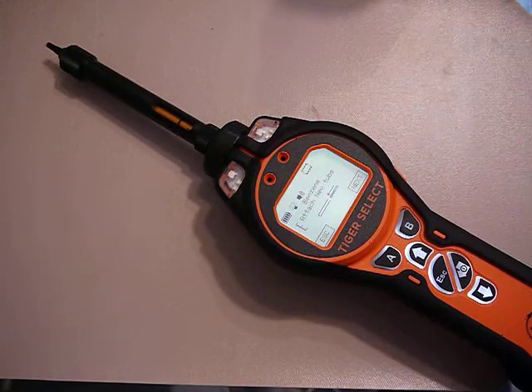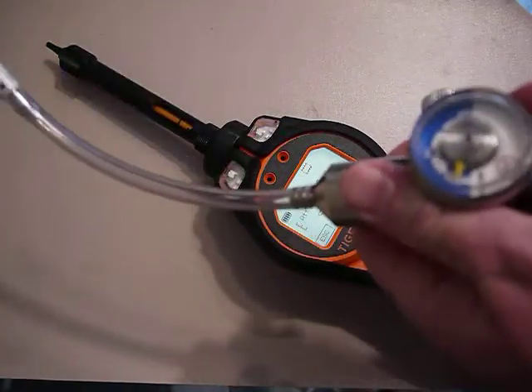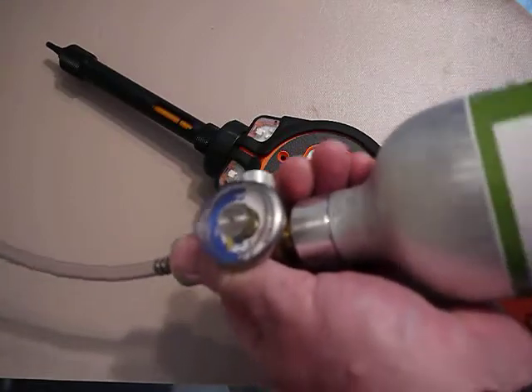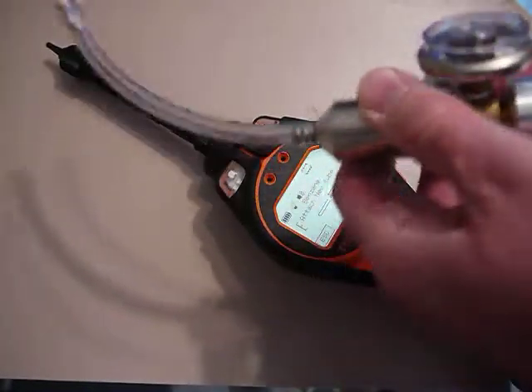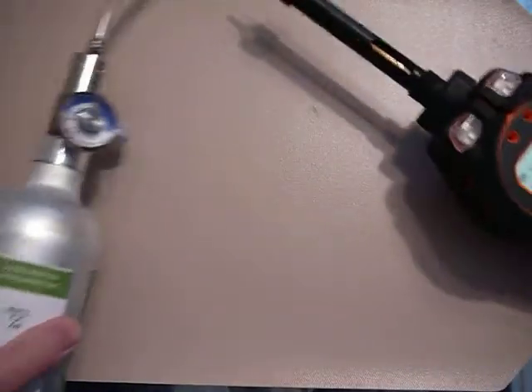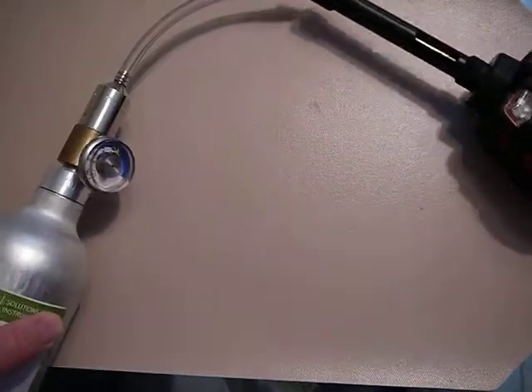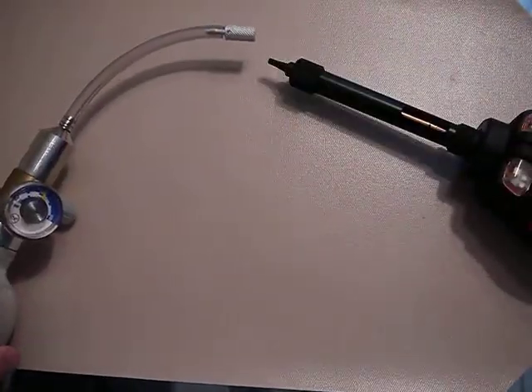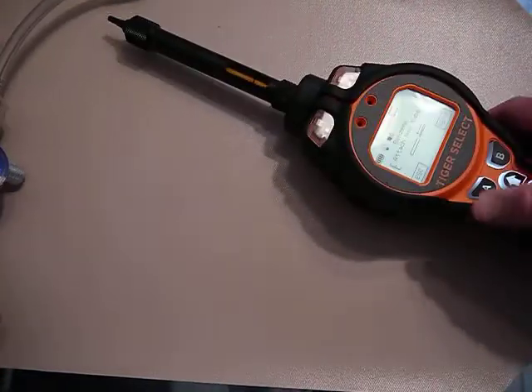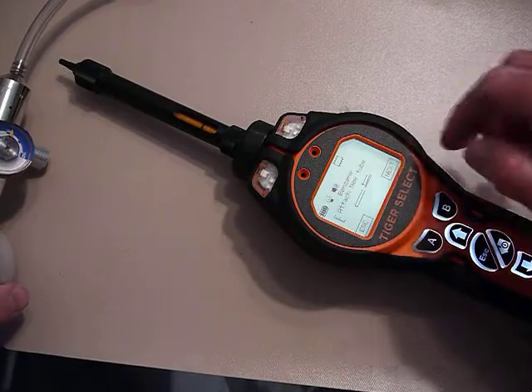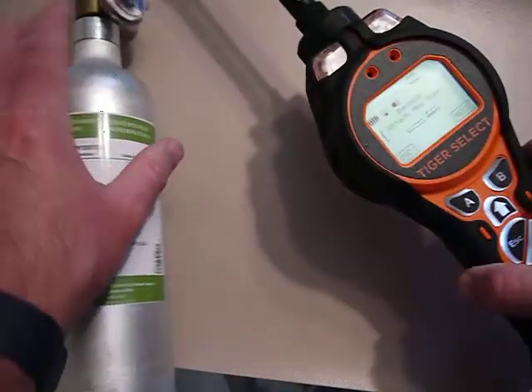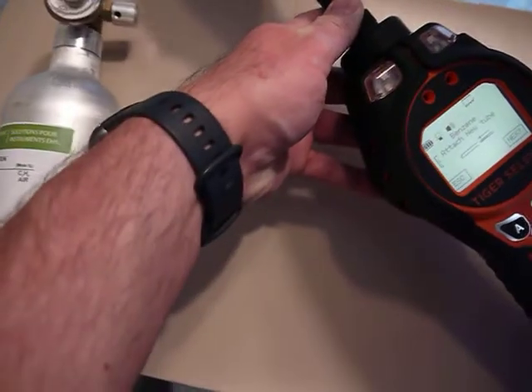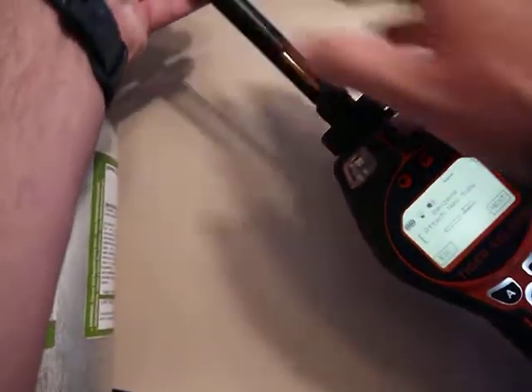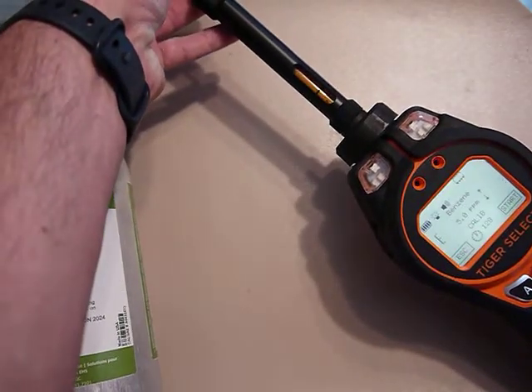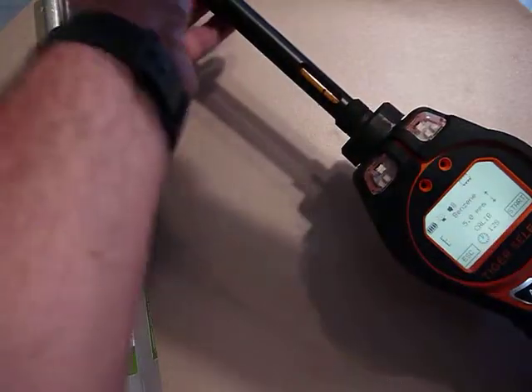I'm just going to get the gas ready though. So I put a 0.5 liter per minute regulator onto a cylinder of 5 ppm benzene. Now you want to do this calibration in a fairly well ventilated area. Note that when you take 5 ppm and put it into a large room, it's not a very high concentration really, but it doesn't hurt to have good ventilation. So let's see here, this might be tough to actually show on camera, but let me just start this. So I'm going to put the tube over the end, okay, and hit next, and now it says start. So I'm going to start the flow of gas.